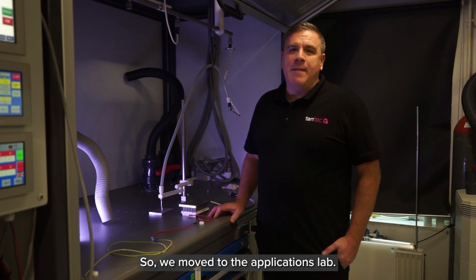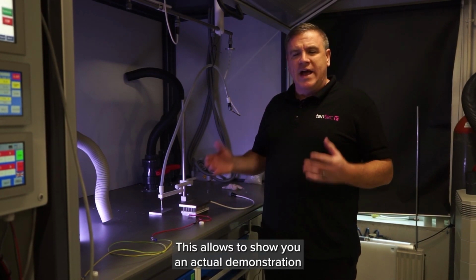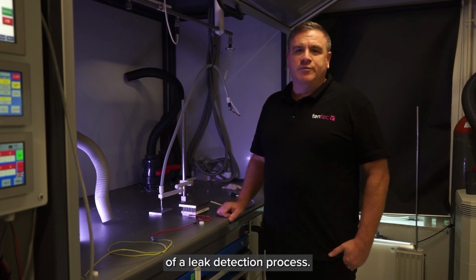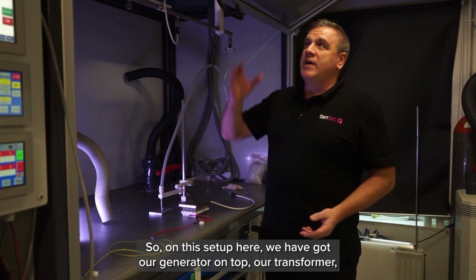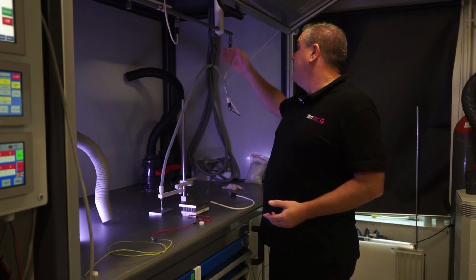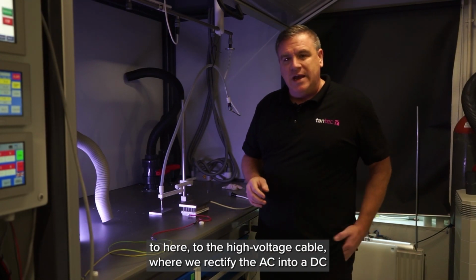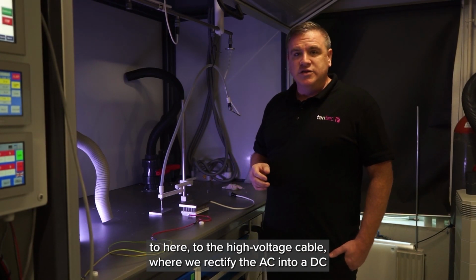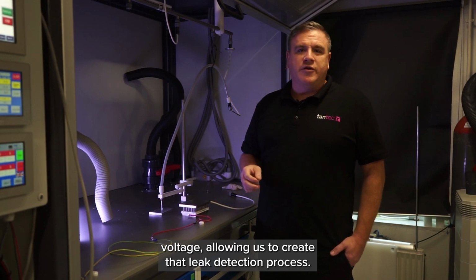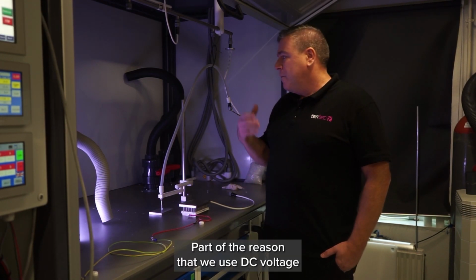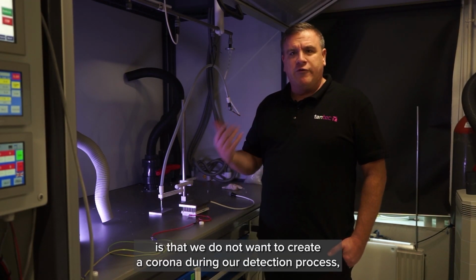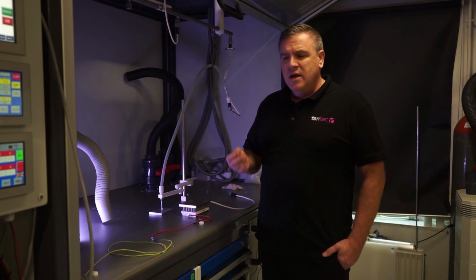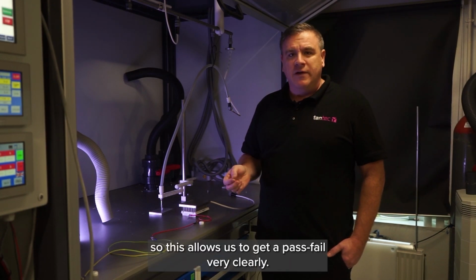So we've moved into the applications lab. This will allow us to show you an actual demonstration of the leak detection process. On this setup here, we've got our generator up top, our transformer. Then we come down through here to the high voltage cable where we rectify the AC into a DC voltage, allowing us to create that leak detection process. Part of the reason we use DC voltage is we don't want to create a corona during our detection process. So this allows us to give a pass-fail very clearly.